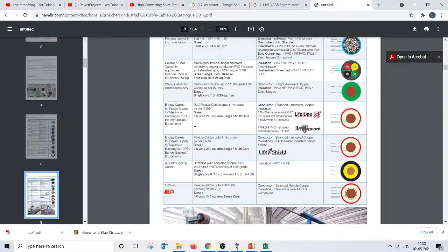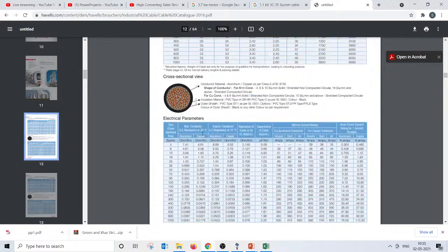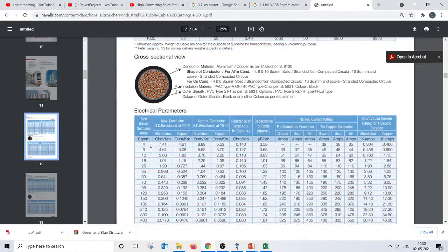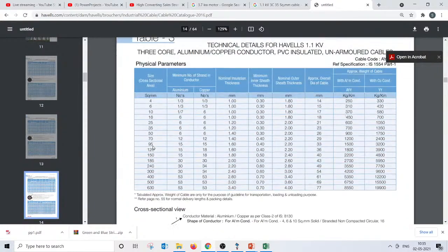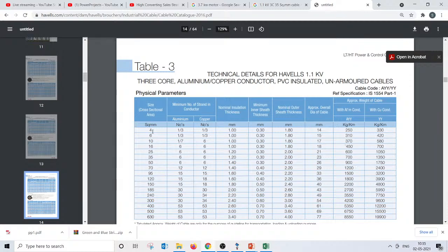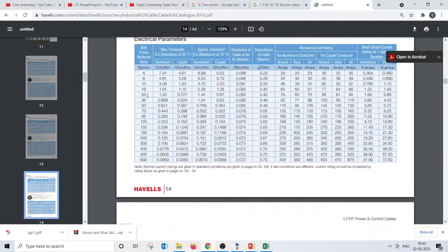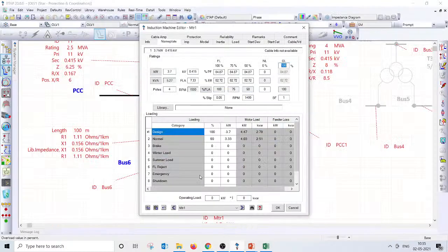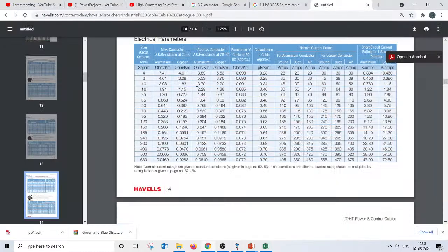I can share that link also in the chat box. Right, you can see the square mm starts at single core 4 square mm. It's a 2 core cable. If you take a 3 core, 4 square mm cable, correct, no? The weight and everything is given, and the current carrying capacity is what we need to look at. A 4 square mm cable can carry easily 28 amps, 23 amps. Even if it is an aluminum conductor, the current carrying capacity is 28 amps or 23 amps in duct or air, even for a 4 square mm, and our requirement is just about 7.33, which means even a 2.5 square mm cable can carry at least half of this current, and even with a derating factor of maybe 30-40%, 2.5 square mm will still do if current carrying capacity is the only issue.